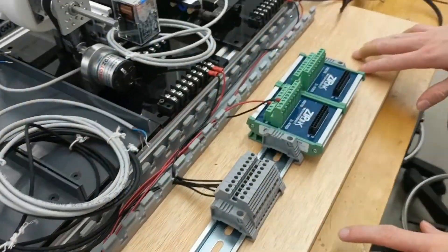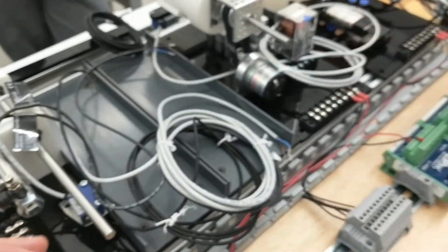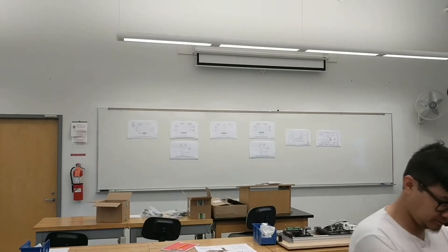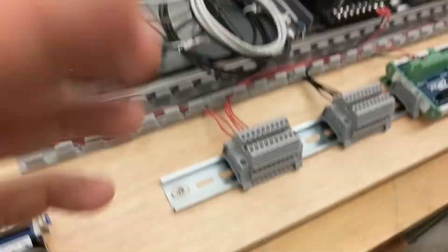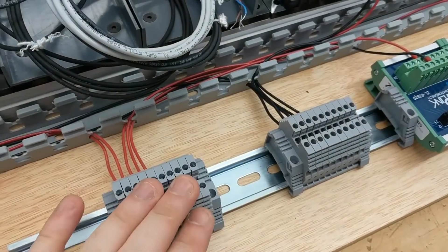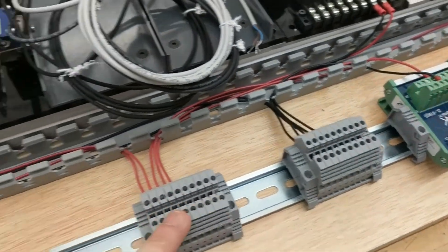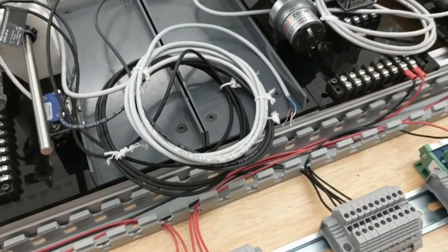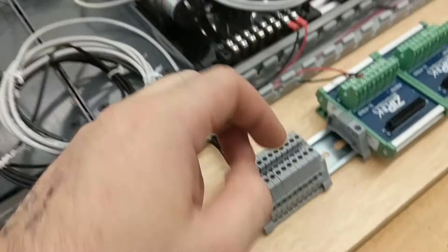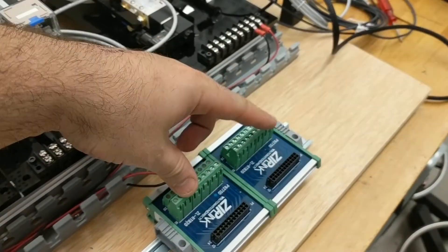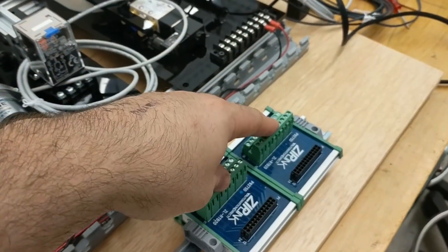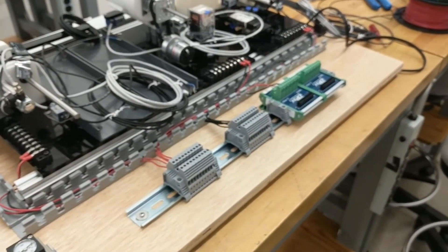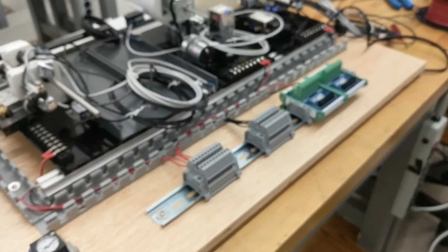On this side of the terminal board, that goes into our sensors and also to the pneumatic solenoids. So I'm following what Will is saying. So what this diagram here, it's the wiring from each of the breakouts from all of this stuff to the modules. And then each individual module has its own wiring diagram, which is just over Patrick's shoulder there. This is the 24-volt bus, this is the zero-volt bus, and our 24 volts is going to each of the modules, and the zero is these are our signals which are going back to the PLC.